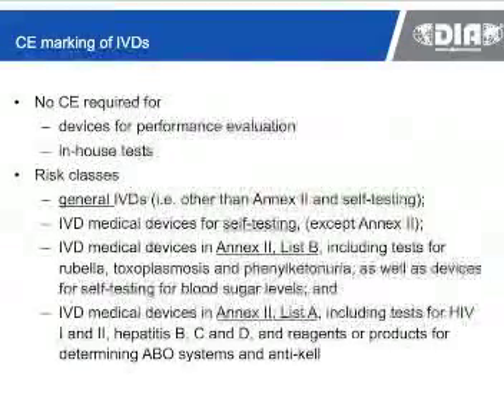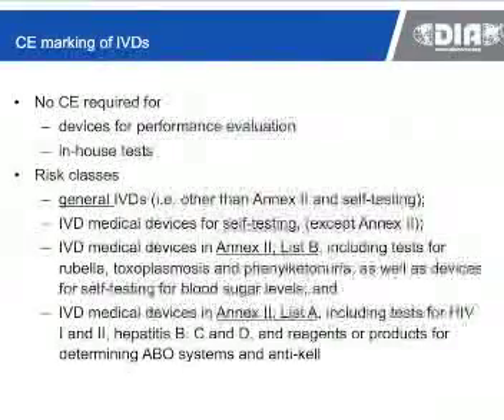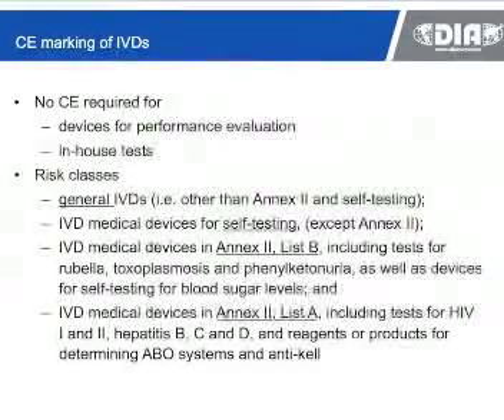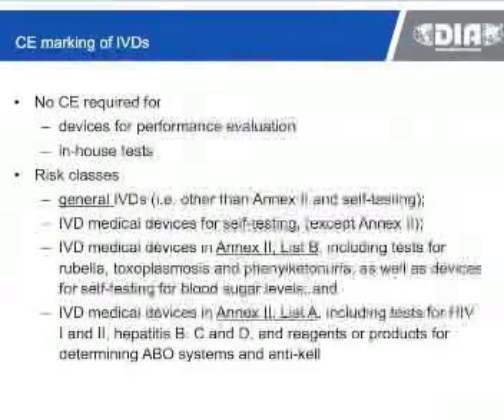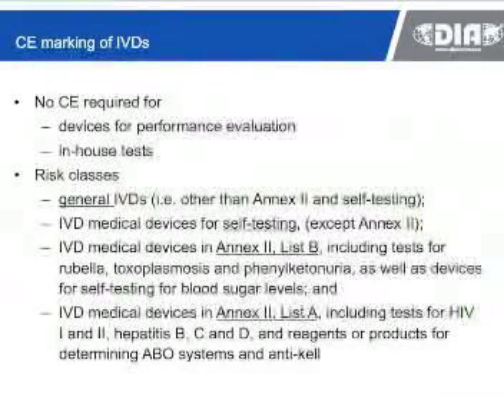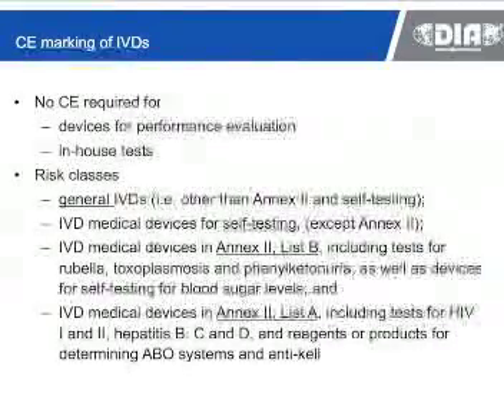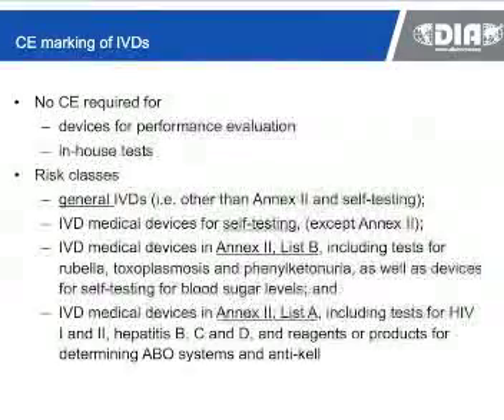So what risk classes do you have for in vitro diagnostics? Because the risk class determines the requirements for conformity evaluation. So there's the general IVDs. This all still applies to companion diagnostics that are an in vitro diagnostic device. So you've got your general in vitro diagnostics, other than those with an indication listed in Annex 2 of the directive, which lists the indications that require intervention of a notified body. Self-testing devices also require intervention of a notified body. Of course, there's also the category of IVDs for self-testing. So think blood glucose meters, for example.